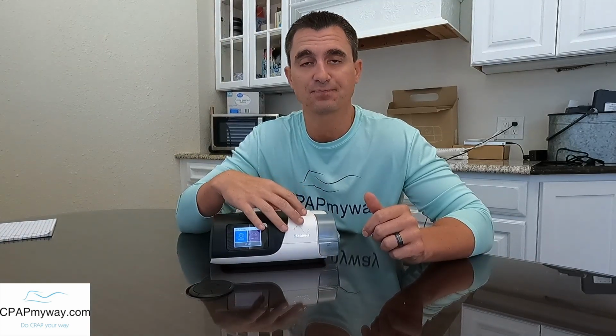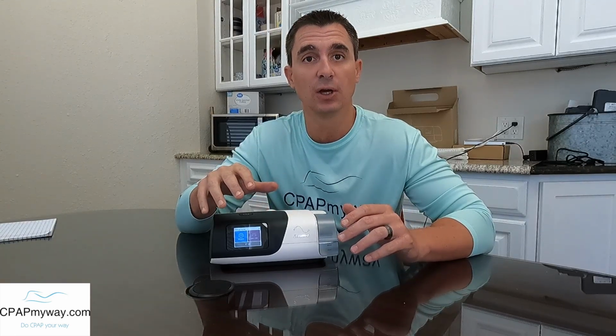In turn, you'll have the exact same amount of water in your chamber the next day. If it's deeming that your room is too cold or couldn't hold extra humidity through the tube for other reasons, like that the air is just not capable of holding on to more, usually that's associated with temperature, right? So like you're not going to be able to run from the humidifier to the mask without causing condensation because your room's cold. In that case, it won't add any water either. But if you're not experiencing any issues, then there really isn't an issue.